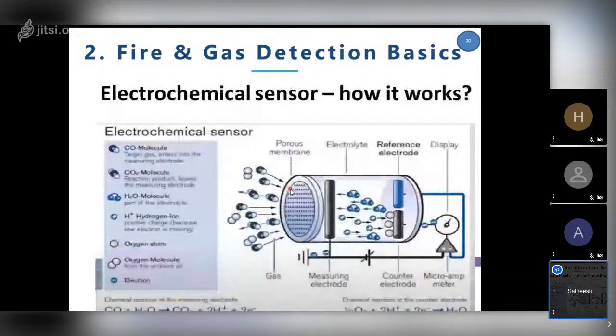To make it quicker, when there's a gas leak, it enters through the sensor membrane, which is the inlet path. Inside there's an electrolyte or chemical, different for the H2S sensor and different for the CO sensor. A chemical reaction happens, and it sends a reference or electrical signal back to the transducer, which in industry we call the transmitter. The electronics give a clear electrical signal showing the reaction happening. Without going deeper into the chemistry, basically the gas reacts with the electrolyte and gives a reading that tells us the ppm of toxic gas detected.